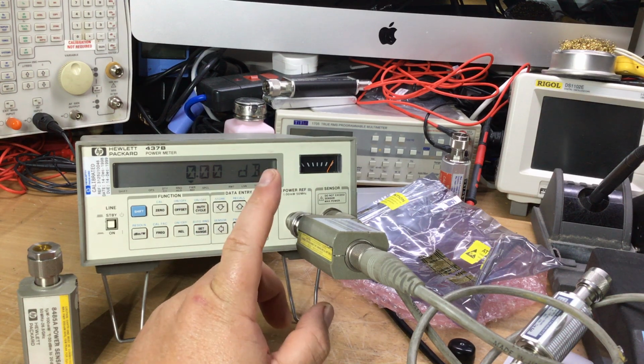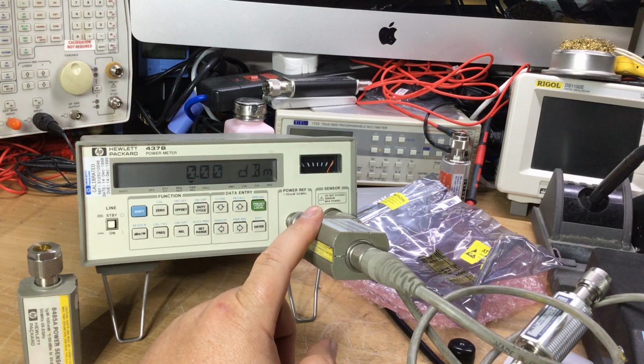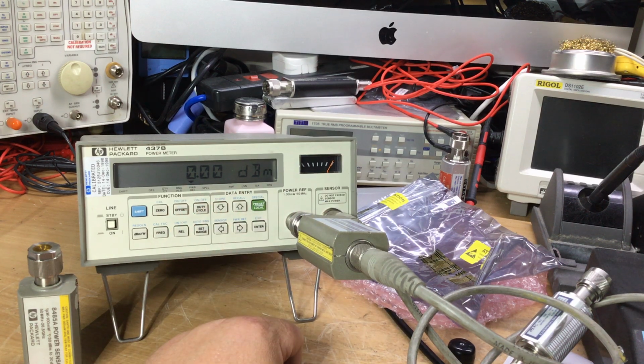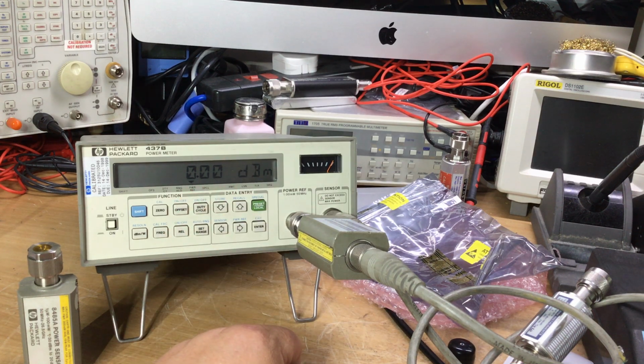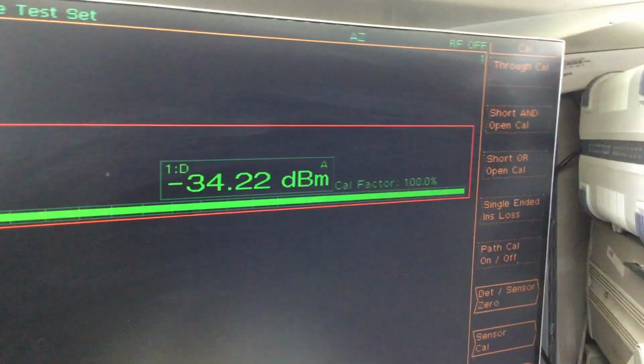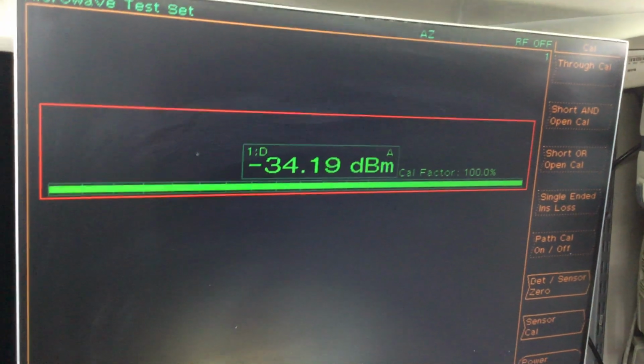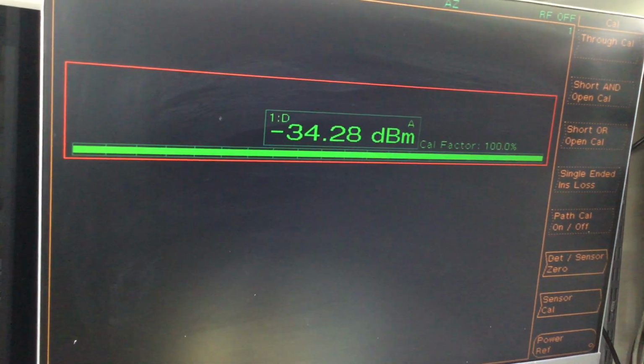So now what we can do is we can do swept frequency measurements on this right up to 26.5 gigahertz, and see what the power meter is reading there at 0 dBm. So we're going to use the microwave test set again, and this time we're going to set up a measurement here where we are going to, if you like, set up a swept frequency measurement.